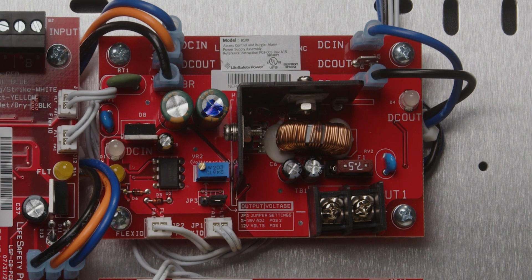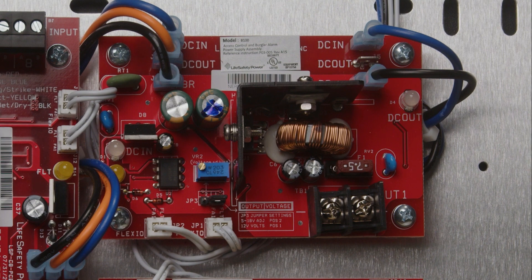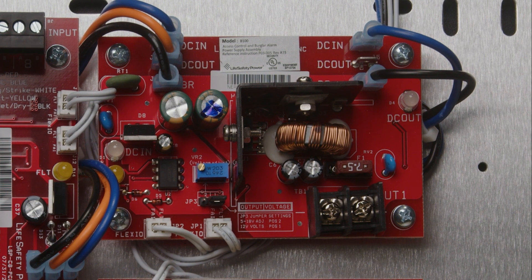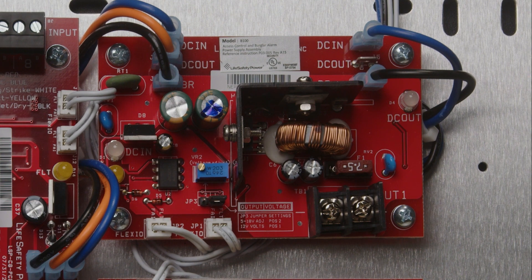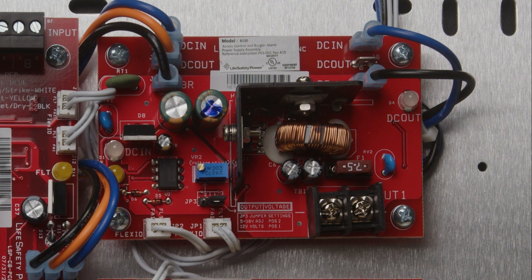You can get the jumper to position 2 on JP3 and use the VR2 voltage adjust. You can change the output value from 5 to 18 volts DC to help overcome that voltage drop in a larger run.